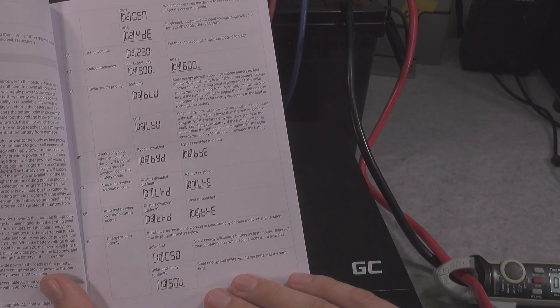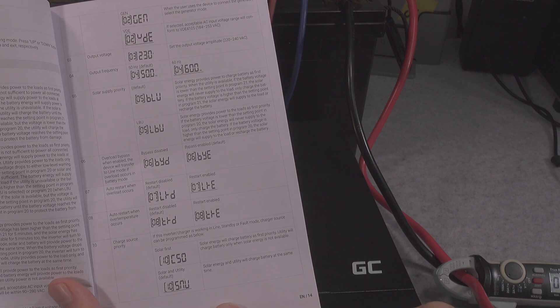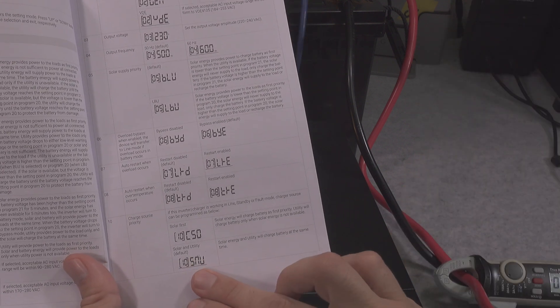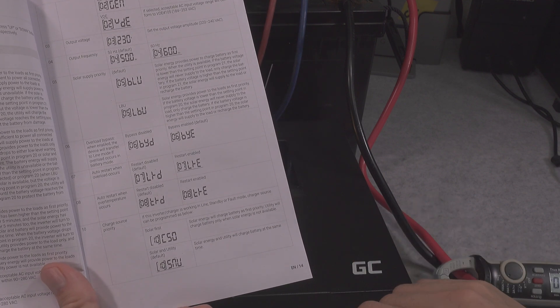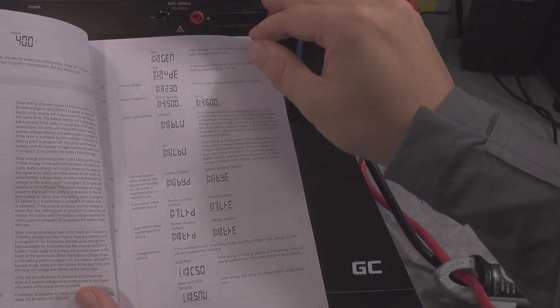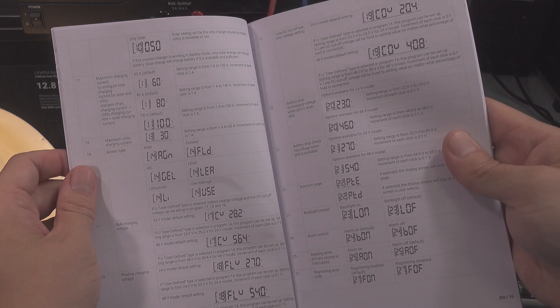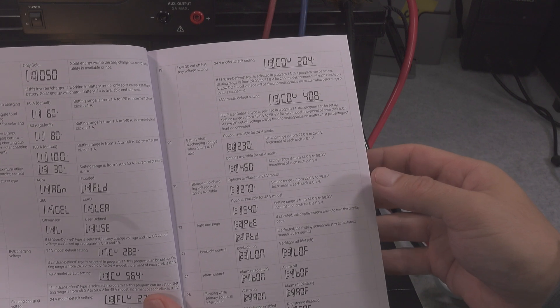Here you can also select the charging source. If you've got a real solar installation, then you would like to be saving money. But in my case, I would like to recharge the battery as soon as possible from the AC and from the power supply, so you can select this. At the same time, the PV and AC is going to be recharging battery. You've got a lot of different settings. I was selecting the proper voltage for the lithium iron phosphate battery, so you go with the lithium ion and you select the bulk and float voltages. I copied that from the Victron Energy manual.